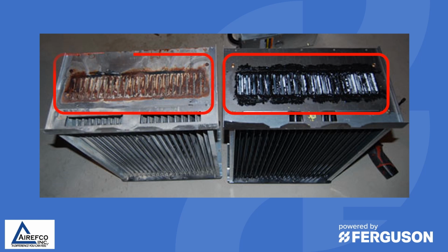This one on the left is definitely a defective heat exchanger, as there is a lot of rust and corrosion and buildup in the panels that is restricting the airflow through the secondary heat exchanger. This heat exchanger would need to be replaced.